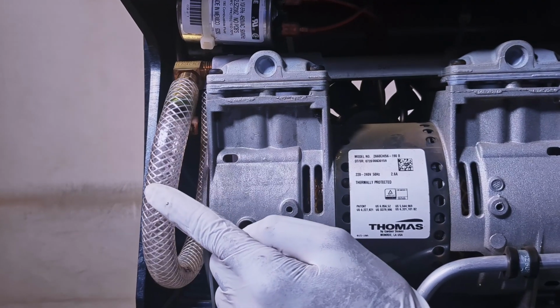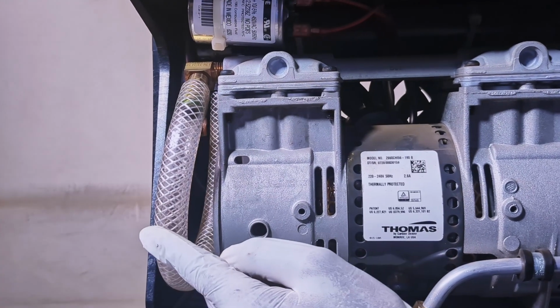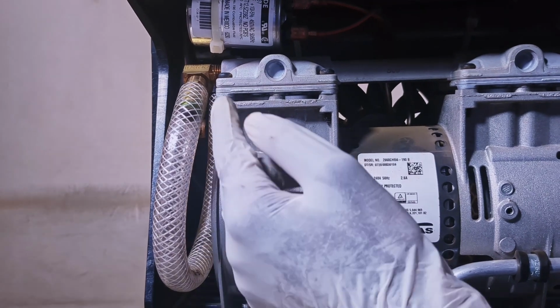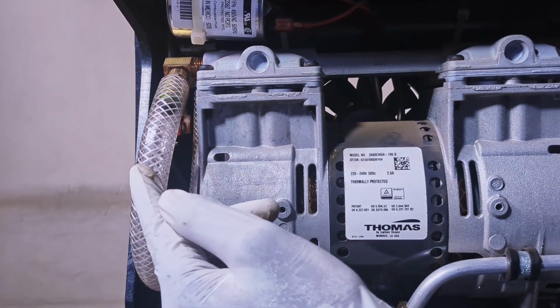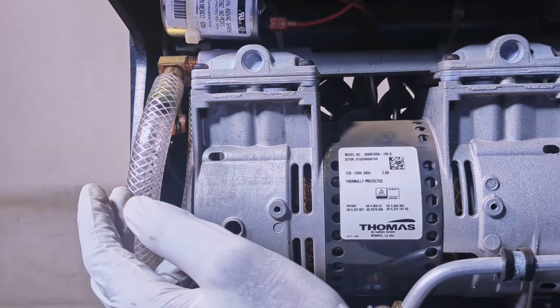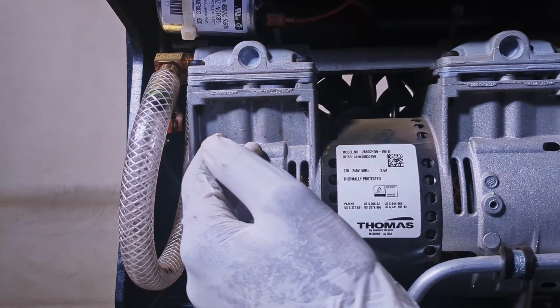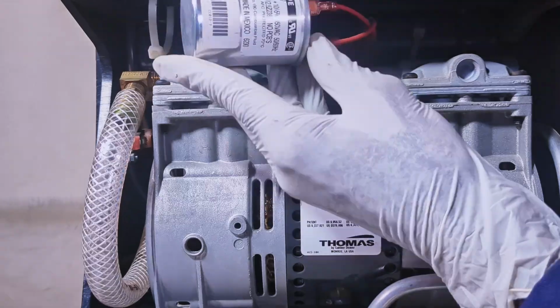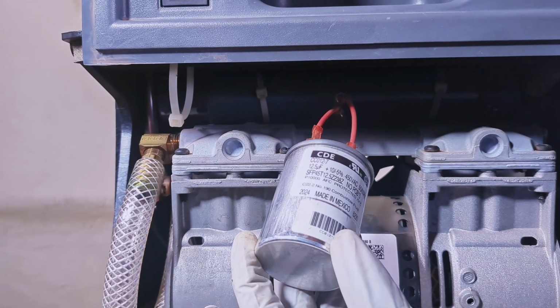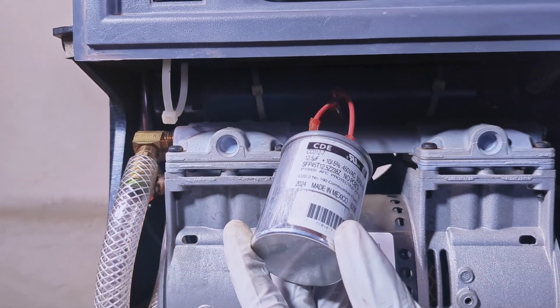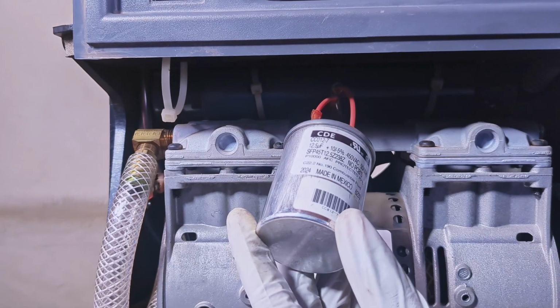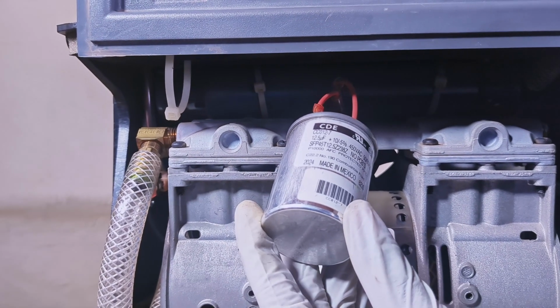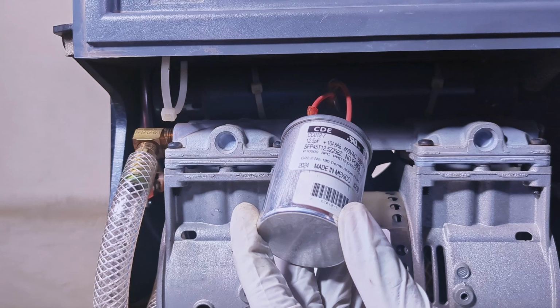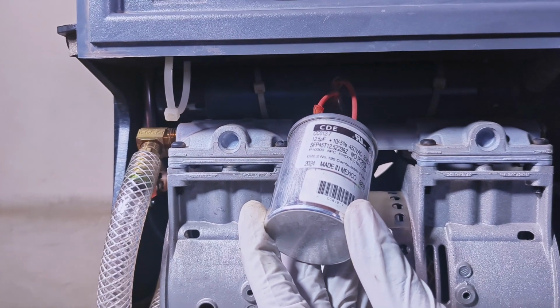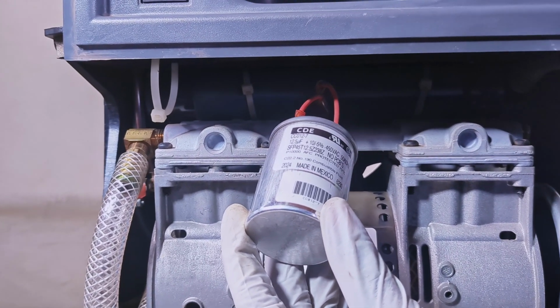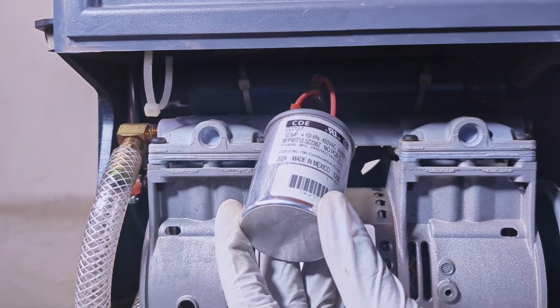Over here we have the intake hose. This one is the one which connects the compressor to the intake muffler, which I will show you in a moment. It is used for bringing air into the compressor. And here we have the start run capacitor. This capacitor is used to start the compressor. It is a 12.5 microfarads capacitor with a voltage rating of 450 volts AC at a frequency of 50 to 60 Hz.